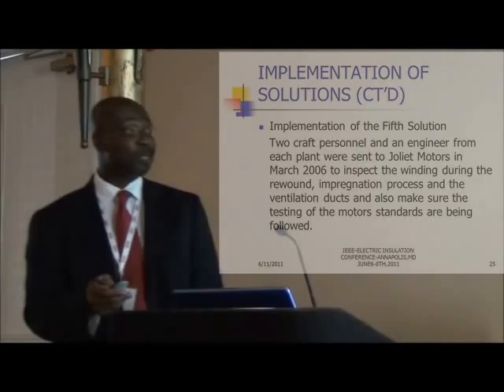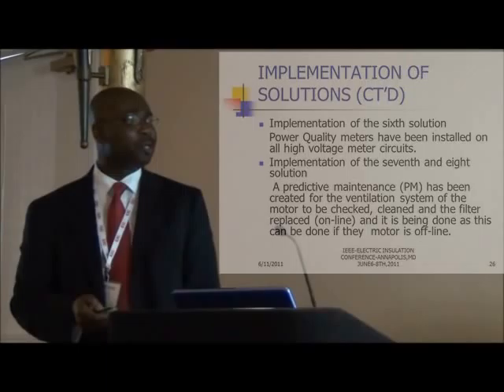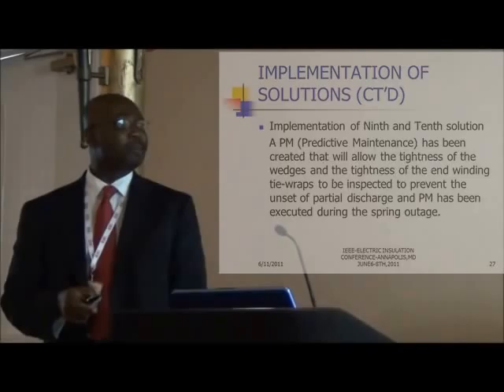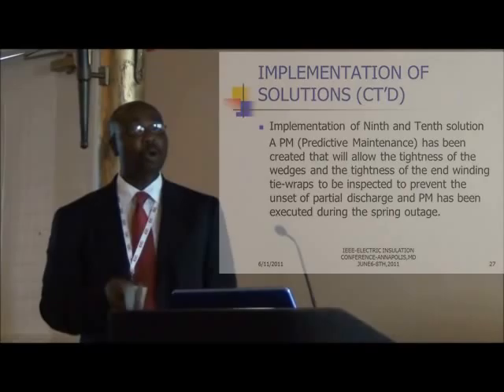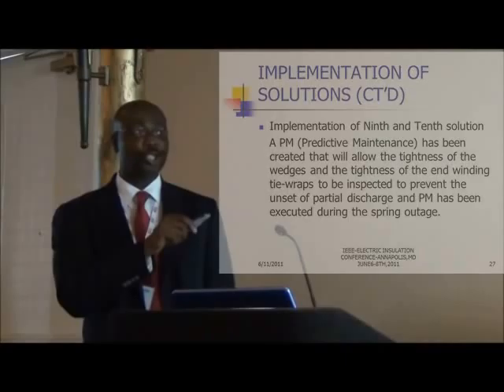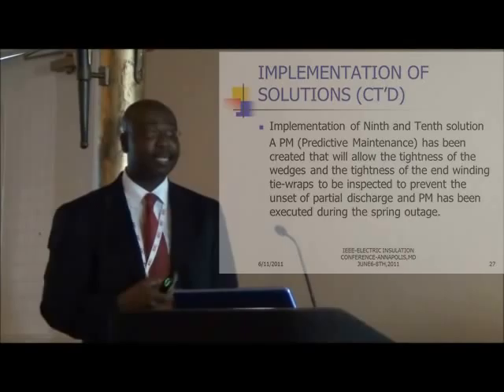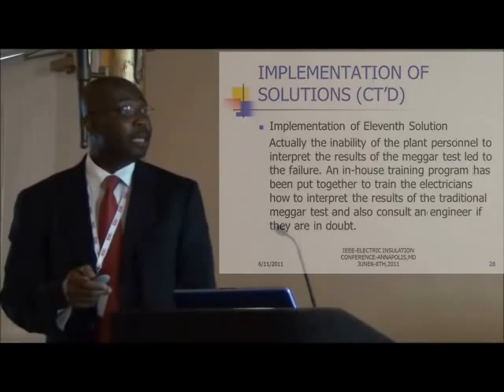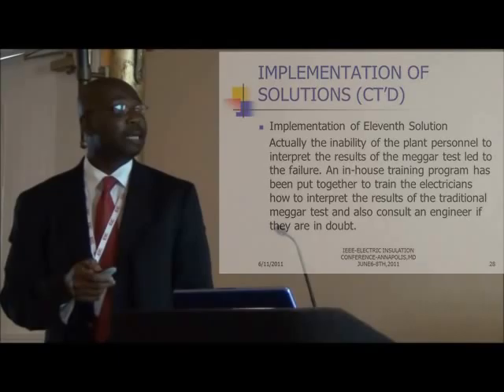Power quality meters were installed in the switchgear. We also created PMs for checking the tightness of wedges and end windings, whether the motor is being repaired on site or in a motor shop. The eleventh solution was in-house training for electricians. That brings the presentation to a close.